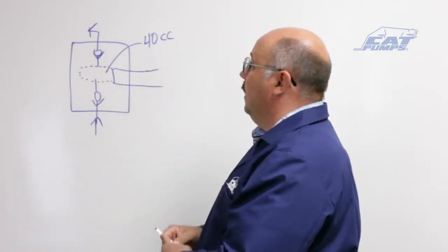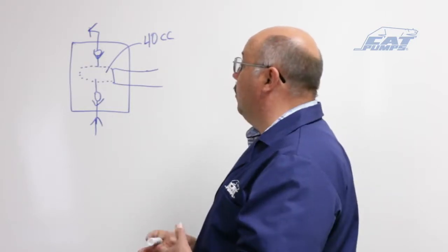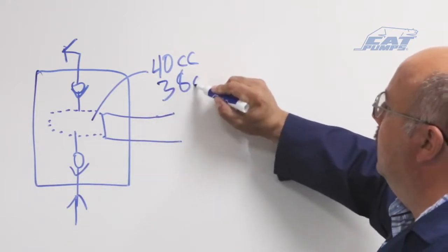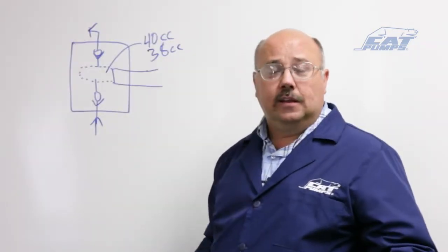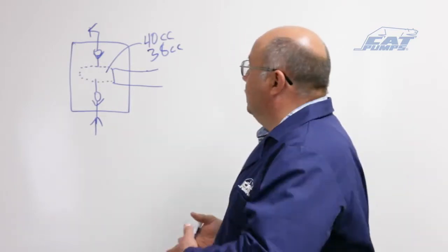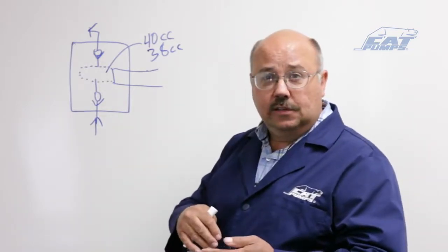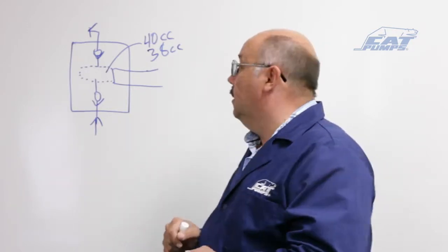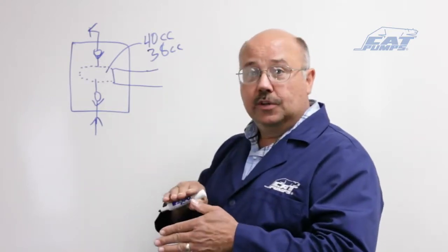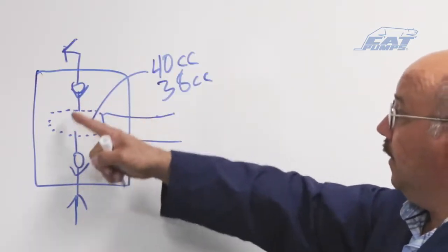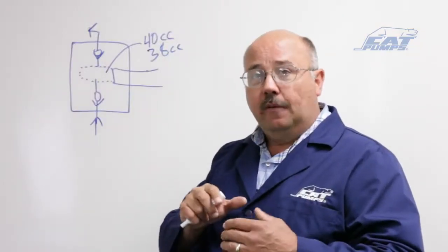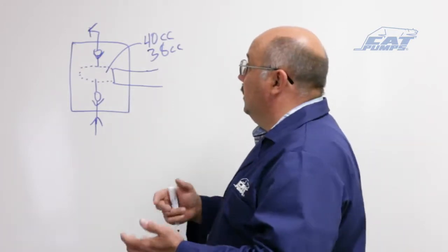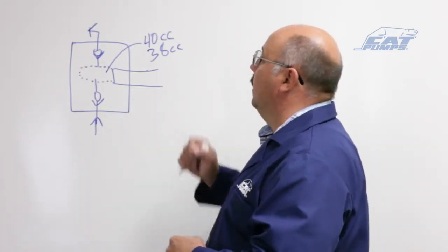If there's something in the nature of the system or the water or the speed, so that when I draw the plunger back, I only get in 38 cc's of water, I have now created a condition called cavitation. I only get 38 cc's of water in there, but what happens to the other 2 cc's of volume that the plunger has moved? Well, you get a low pressure regime in some part of this pumping chamber, and it will change a few drops of the water from liquid phase to a gas phase. So it's changing the state of the fluid.